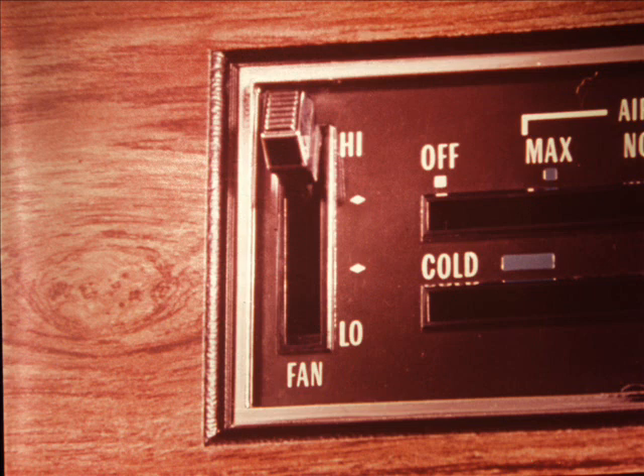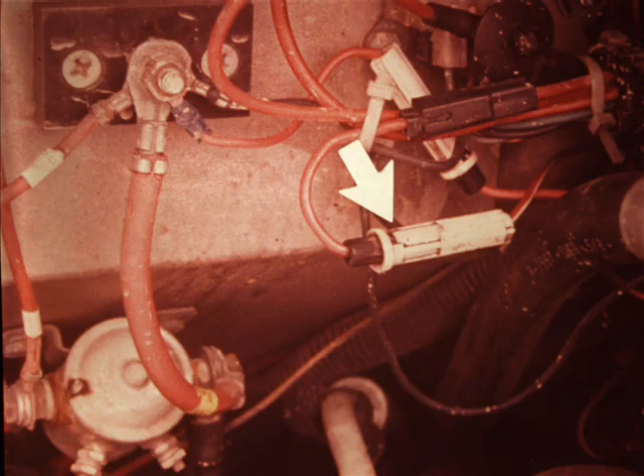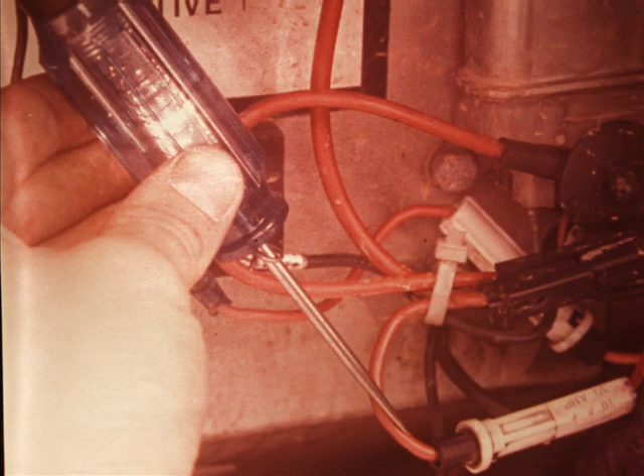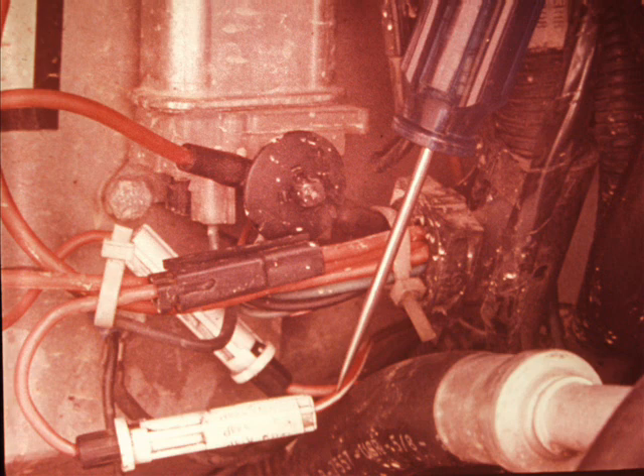A specific open circuit problem that you should be aware of is failure of the chassis air conditioning blower to operate on the high blower setting only. The usual cause is an open inline fuse that feeds the blower motor full voltage when the blower relay is energized in the high position of the switch. To diagnose it, open the right-hand access door, locate the fuse holder, and test for power in and out. If power in is okay, but there's no power out, the fuse is open.